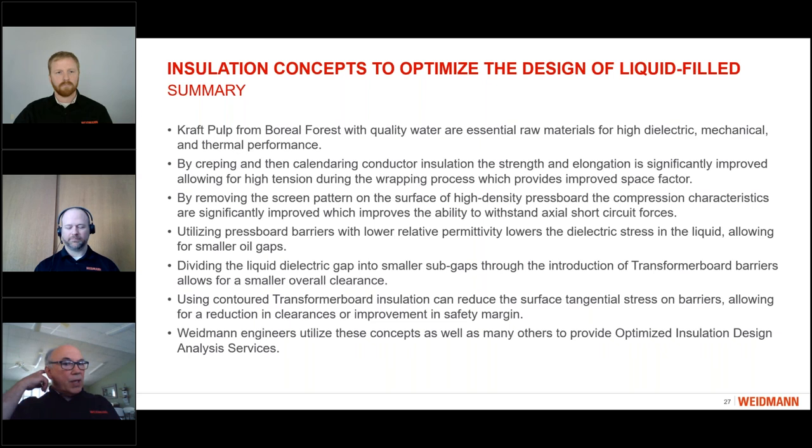The second concept is that by creping, which is putting these folds in the paper, and then calendaring, now pressing those back out, we can add to the strength and elongation of the paper and improve that so that while the paper is wound onto the conductors themselves, they can be wound under high tension, which allows you to have an improved space factor in your winding.